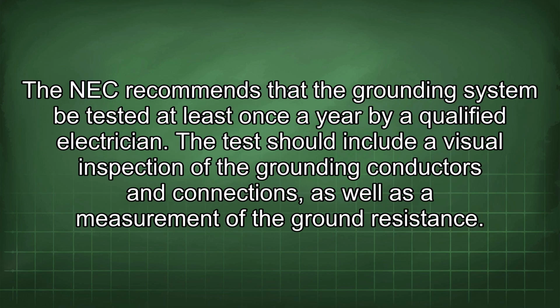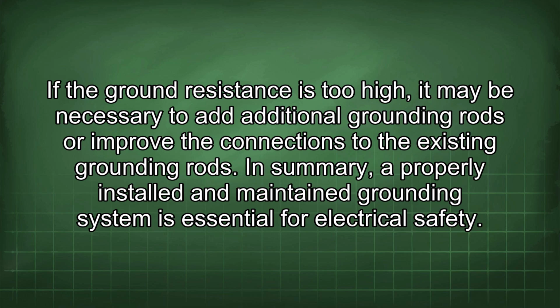The NEC recommends that the grounding system be tested at least once a year by a qualified electrician. The test should include a visual inspection of the grounding conductors and connections, as well as a measurement of the ground resistance. If the ground resistance is too high, it may be necessary to add additional grounding rods or improve the connections to the existing grounding rods.